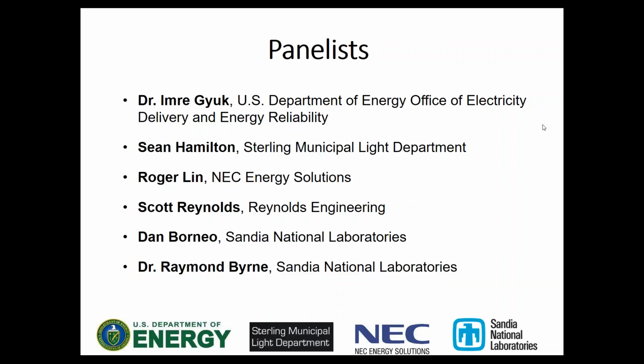In this case, we've got lithium-ion batteries that'll last for about 4,000 full discharge cycles, meaning that if you have 3.9 megawatt-hours in the battery, you can charge and discharge 3.9 megawatt-hours thousands of times before it reaches an end-of-life condition.